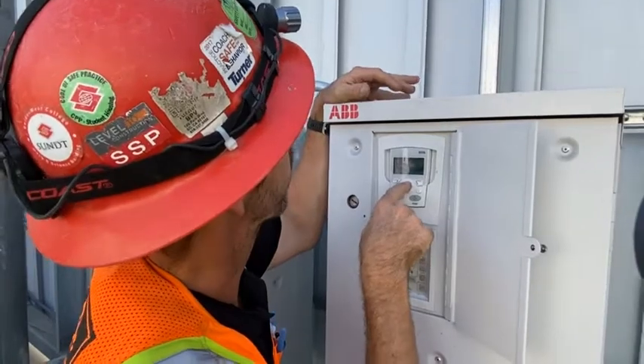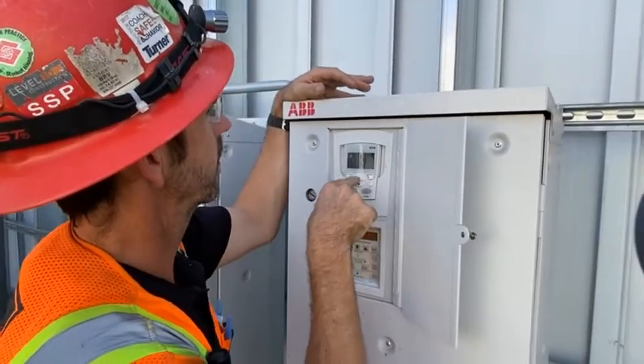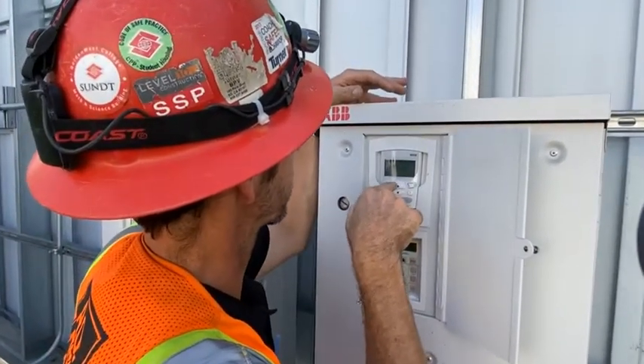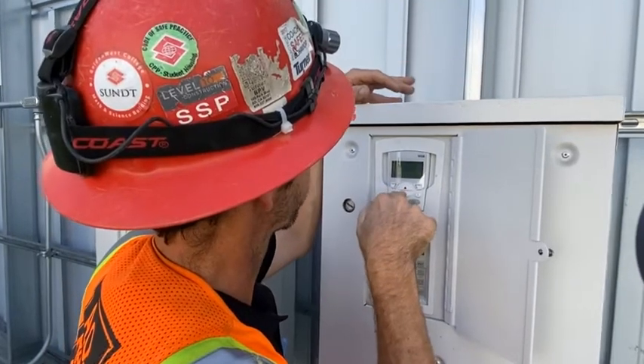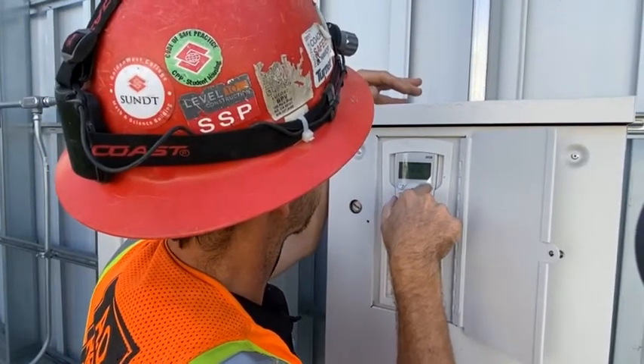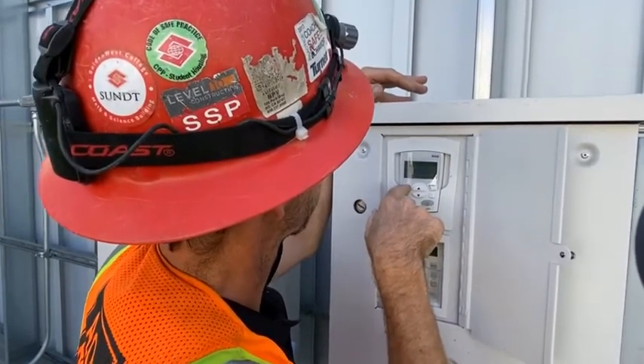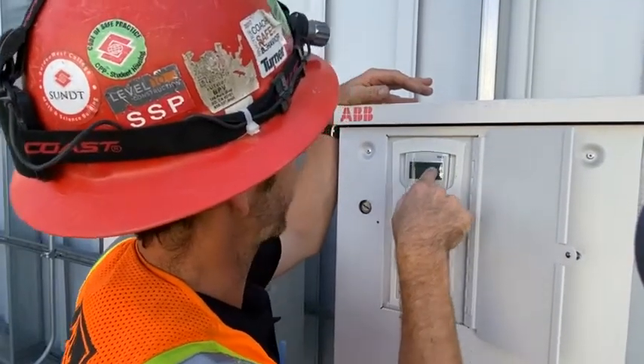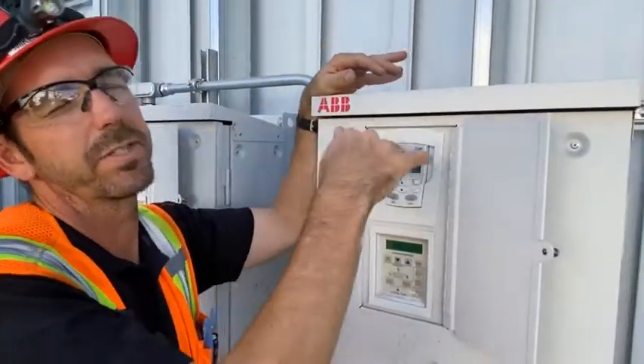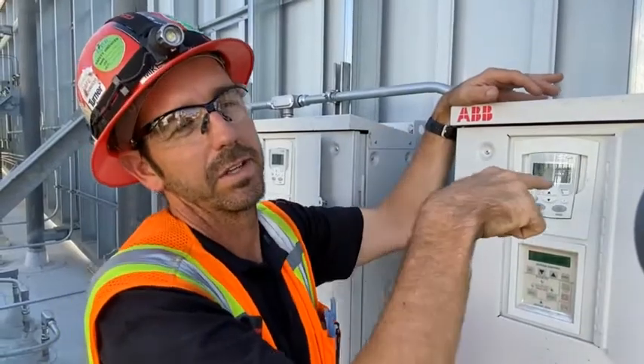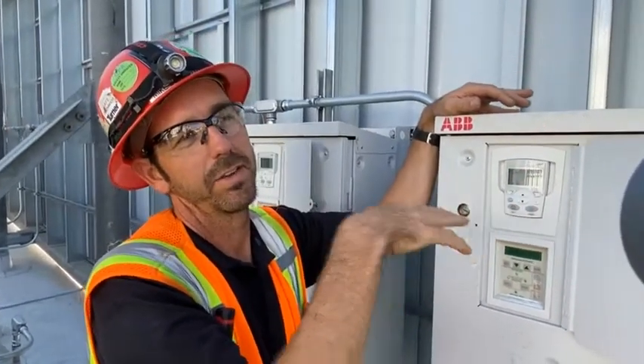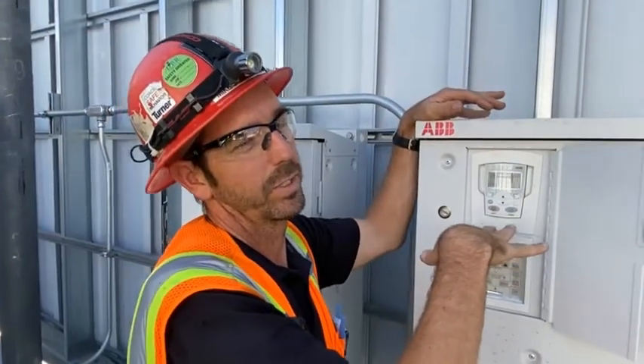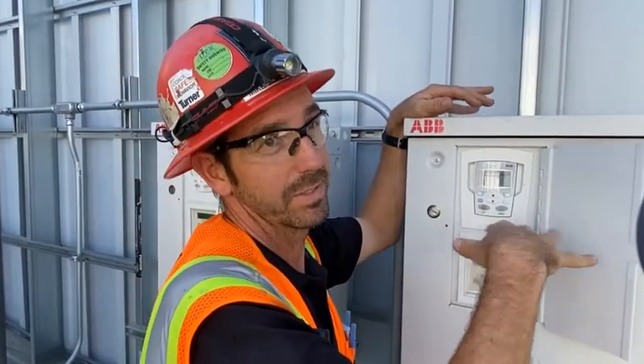I totally messed that up. We want to change number 1. Sorry about that. So we need to get back into panel display. We're changing percent speed to hertz. Normally I change the very bottom one, which is in 4 to 20 milliamps, to 0 to 10, okay?